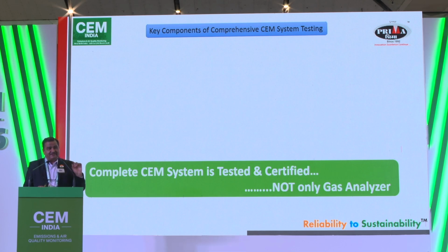The certification is not only for the analyzer; that may be only a part of the certification. When you say my CEMS, I call it a continuous emission monitoring system. I never say continuous emission monitoring analyzer. So when it is called CEMS certification, it means a complete system, starting from your probe, gas sampling system, conditioning device, controllers, analyzers, your PLCs, HMIs. Your software also has to be a part of the certification, and your data transmission has to be a part of the certification program.